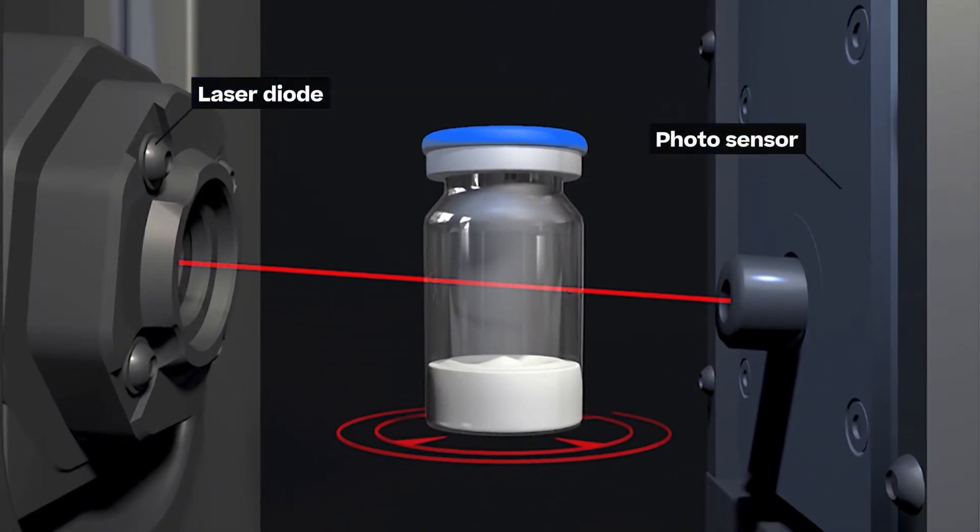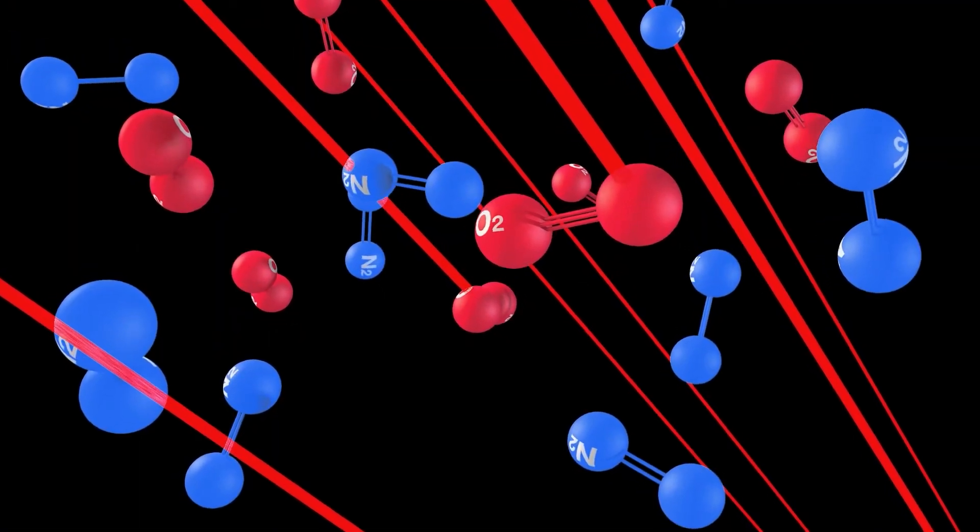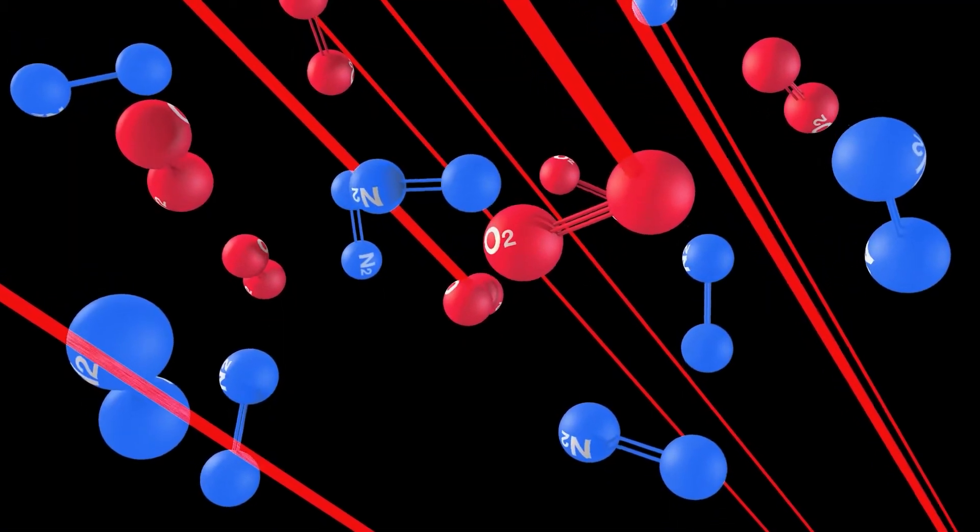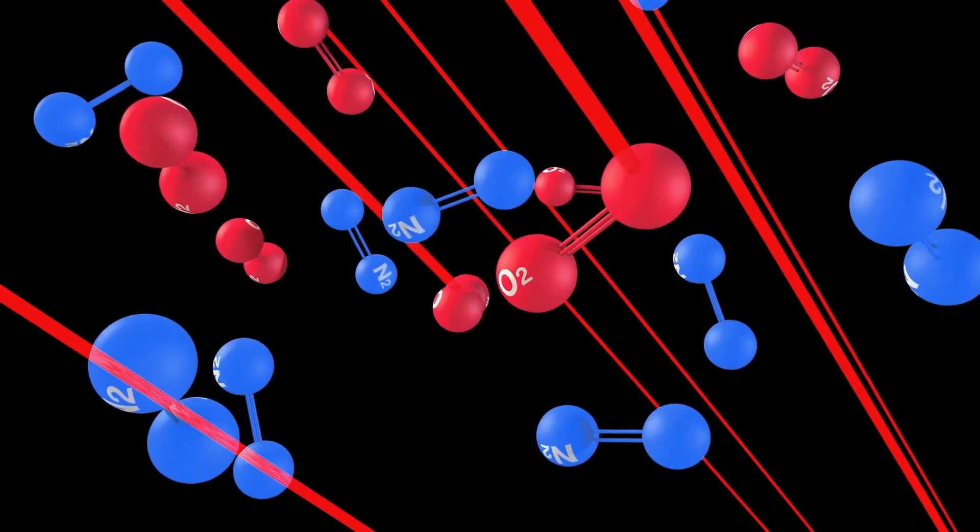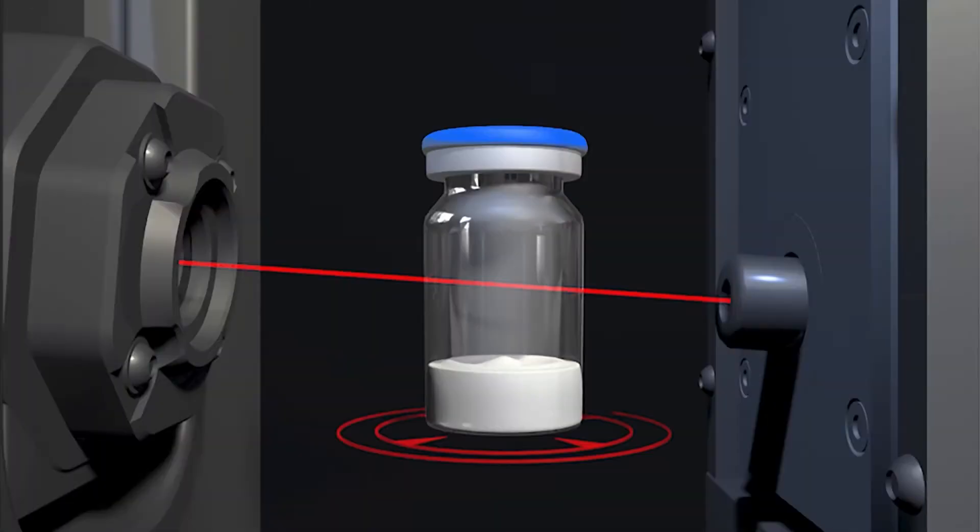A laser beam tuned to a specific wavelength range is directed through the vial above the lyocake. Oxygen molecules absorb a specific wavelength. The more oxygen the vial contains, the greater the deviations from a predetermined limit value.